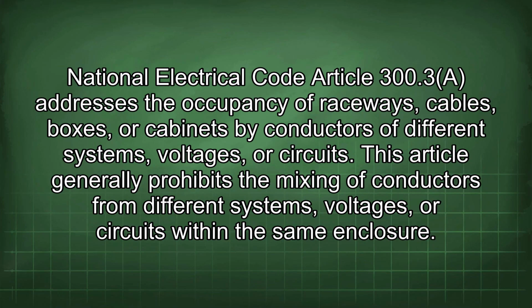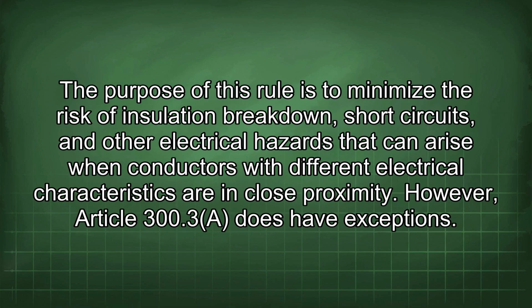National Electrical Code Article 300.3 addresses the occupancy of raceways, cables, boxes, or cabinets by conductors of different systems, voltages, or circuits. This article generally prohibits the mixing of conductors from different systems, voltages, or circuits within the same enclosure. The purpose of this rule is to minimize the risk of insulation breakdown, short circuits, and other electrical hazards that can arise when conductors with different electrical characteristics are in close proximity.